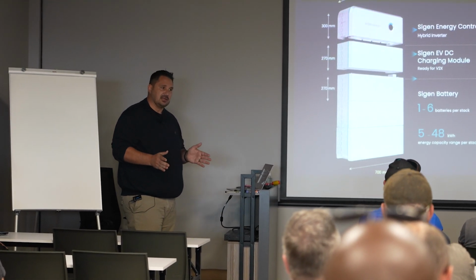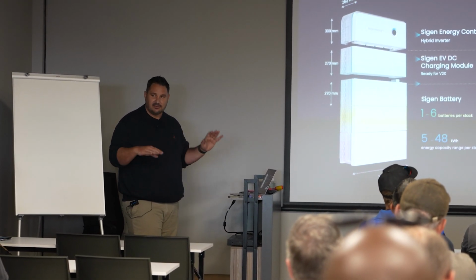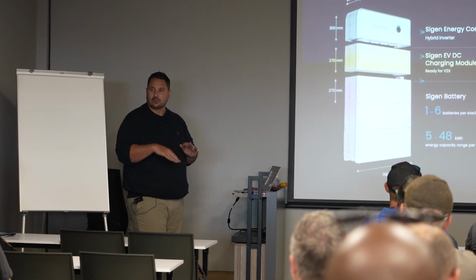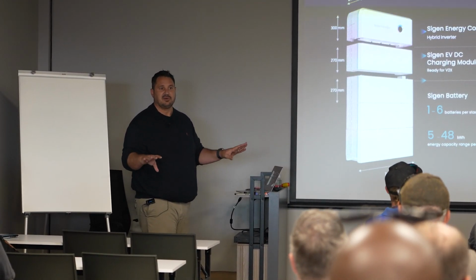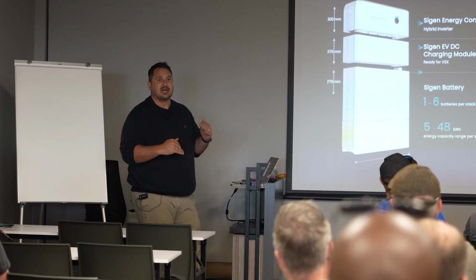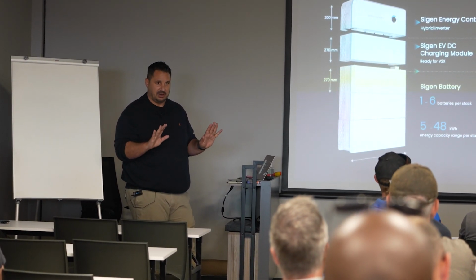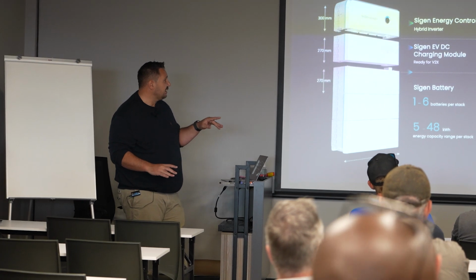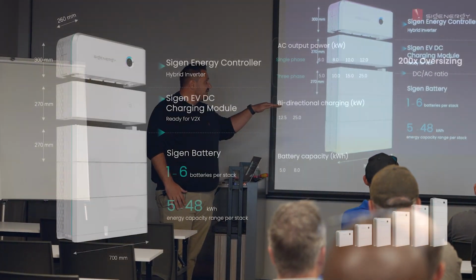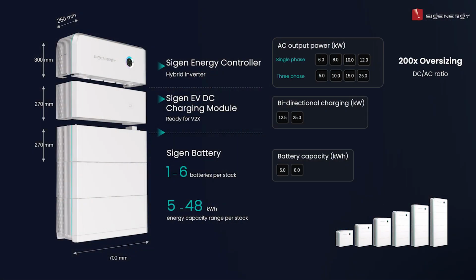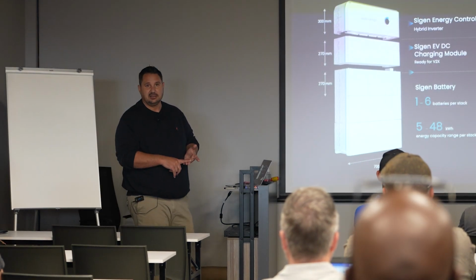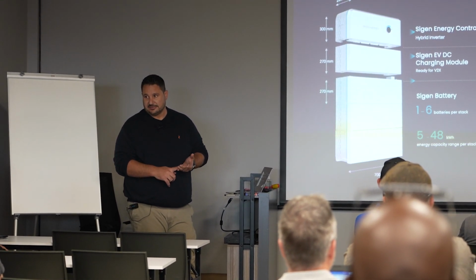So you can mix and match on single phase any different sizes together, and on 3-phase also any different size. So you can do a 25 and a 5, and that'll give you 30. You do not have to have the same inverters when you run them in parallel. Okay. Then on your batteries, currently available 5 and 8 kilowatt hour. We only stock the 8 kilowatt hour, and then 10 kilowatt hour will be available in January. So the batteries will also only be 270 by 260 by 700. Doesn't matter if it's a 5 or 8 or 10, they will always be the same size.